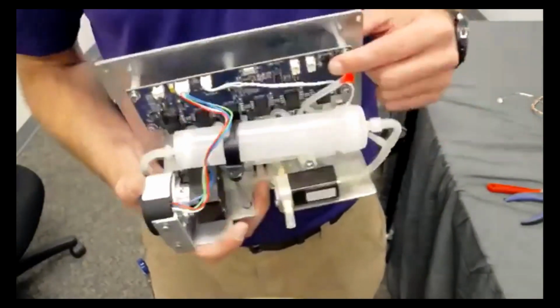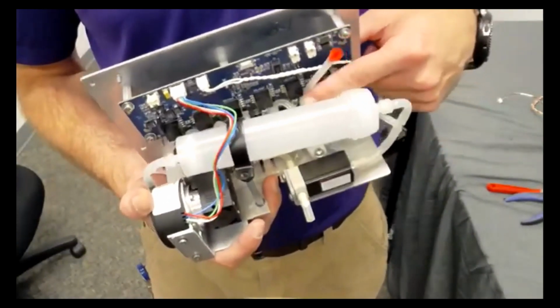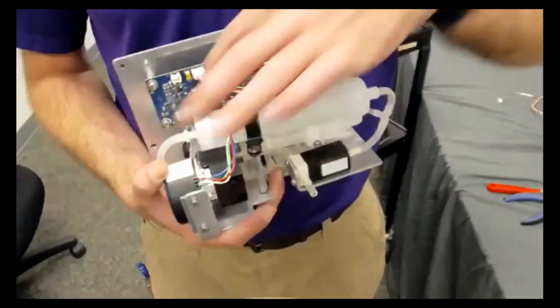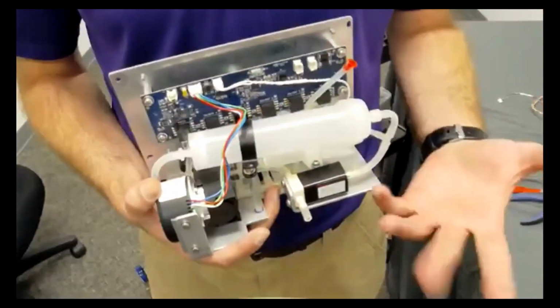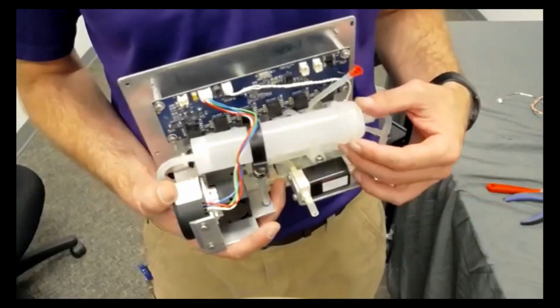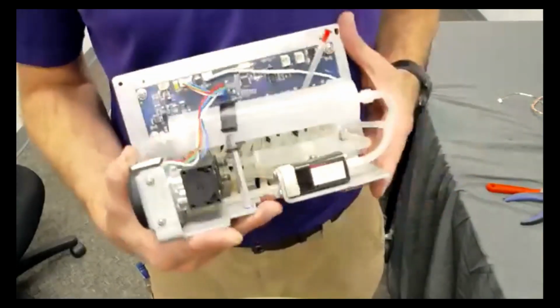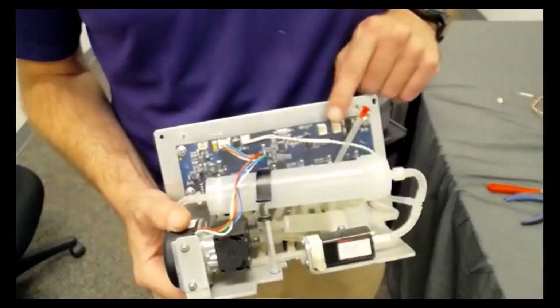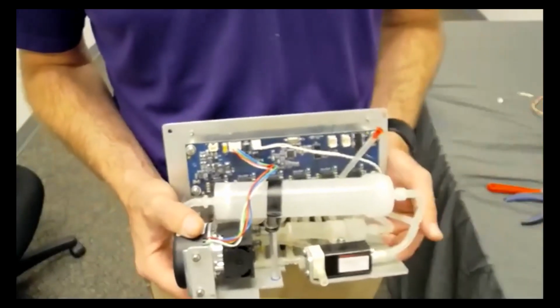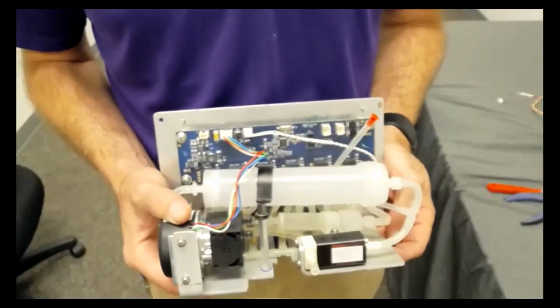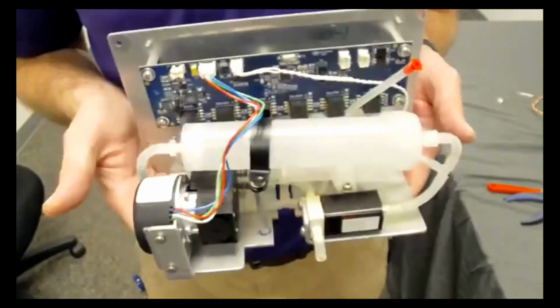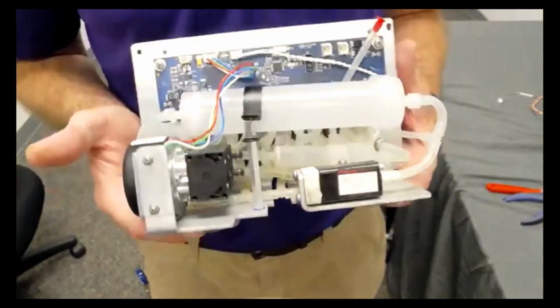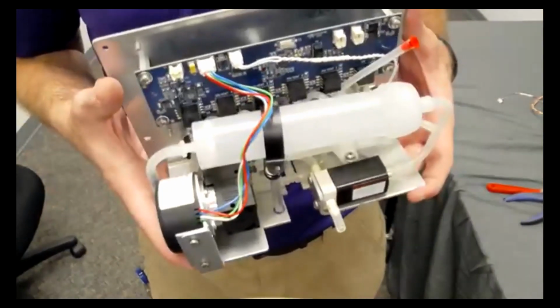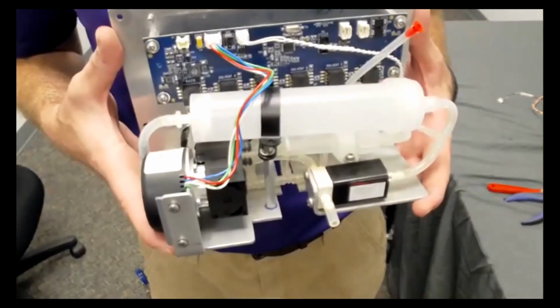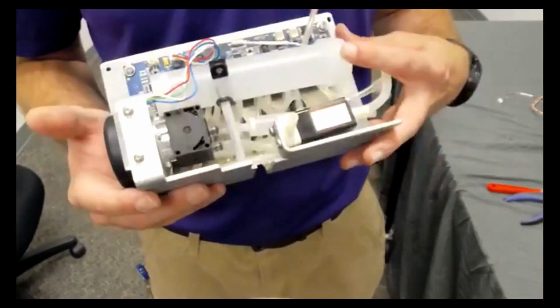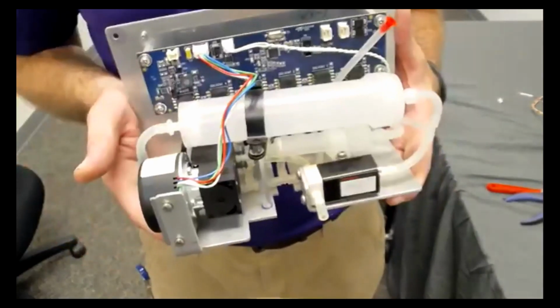This is the main circuit board here, and there are pressure transducers that are sensing how much air pressure is needed to make bubbles in the solvents, as we kind of talked about. That's the air system in a nutshell. There's a cord that plugs in here that goes up to one of those pump boards that we talked about in the left side panel. That's the air system. Won't always be there. It's an option on the 300. Actually, no, I don't think it is anymore. I think it's standard. I'd have to check on that. But that's the air system in a nutshell.